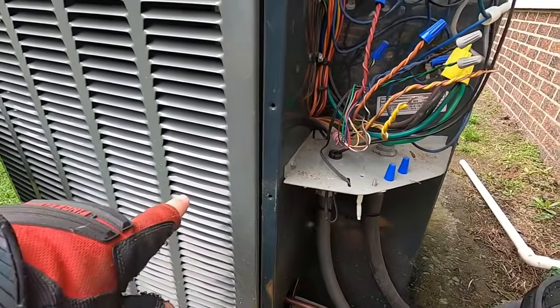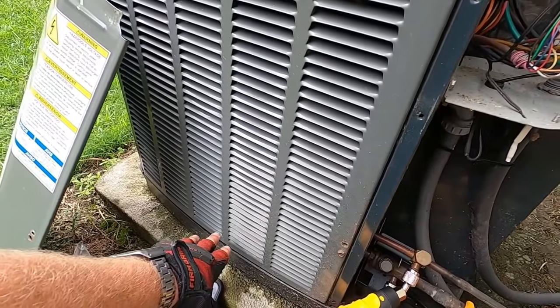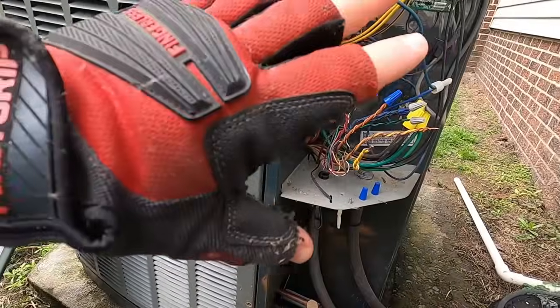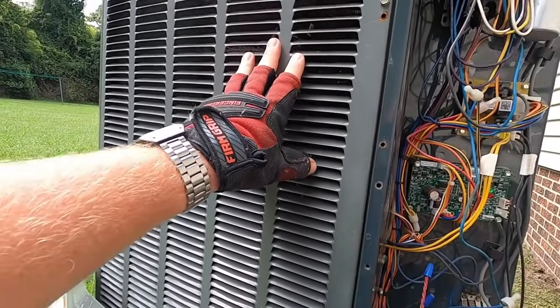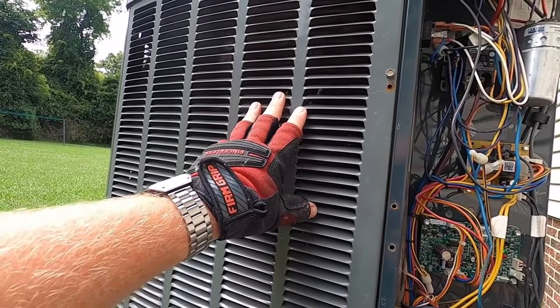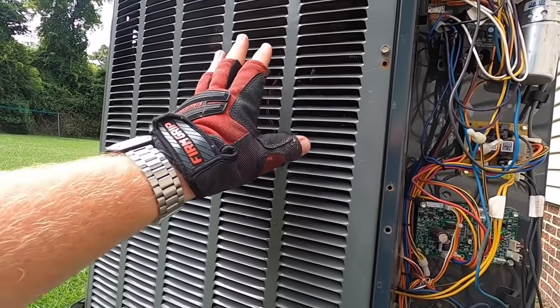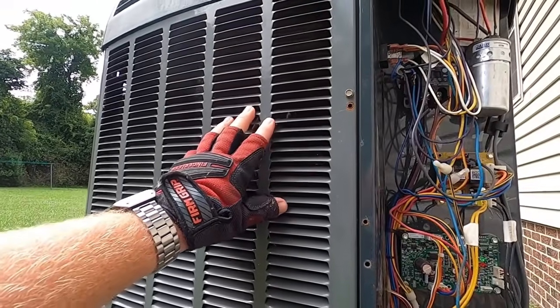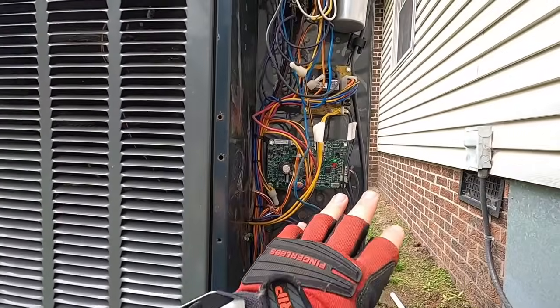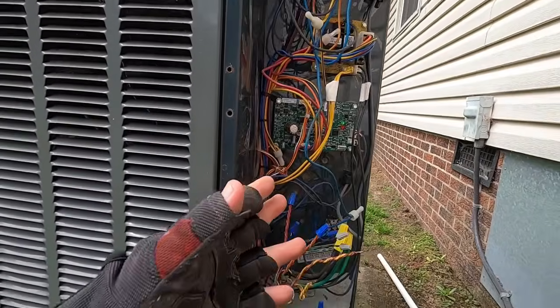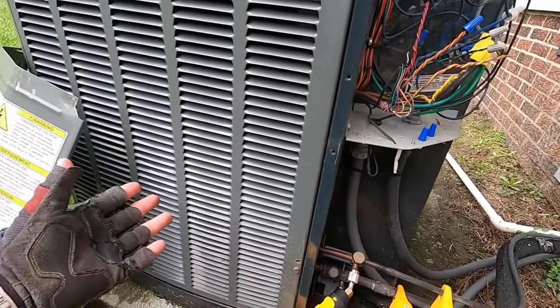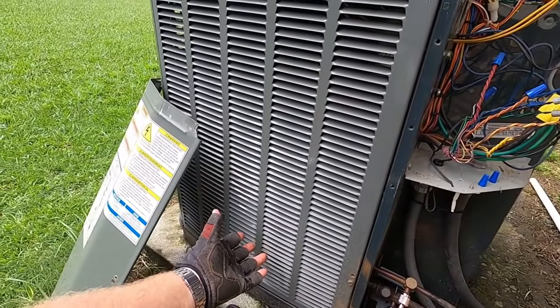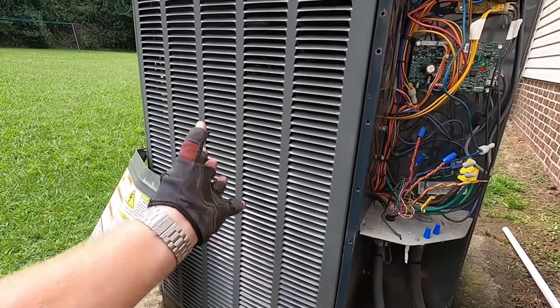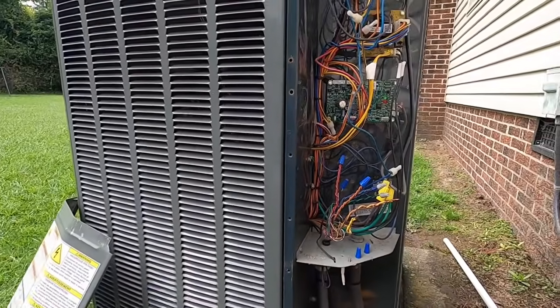I'm not going to take the side panel off, but there is a stepper motor and an EEV in there. There's a suction pressure transducer in there, and then a suction line temperature sensor on the true suction line. So when you run this in heat mode, this valve obviously is your outdoor EEV, TXV, whatever you want to call it. That's your refrigerant flow gets regulated out here in heat mode. And then that transducer that's reading your suction pressure, translating it into a temperature, same way you do on your gauges. Then you got your true suction line temperature reading the suction line, so it's maintaining superheat on this outdoor unit when it runs in heat mode.